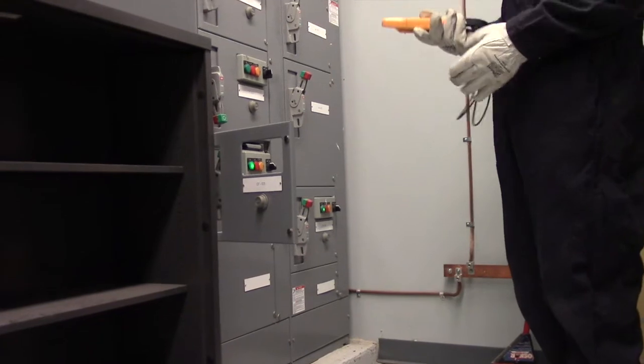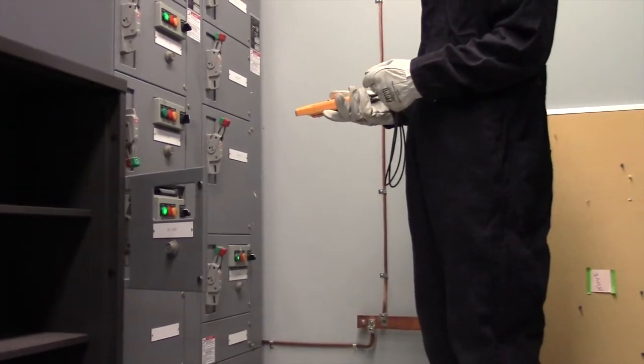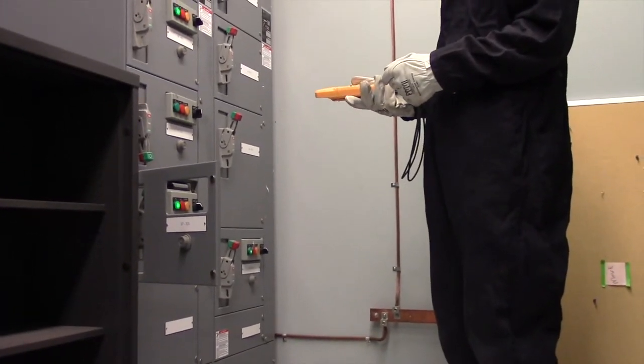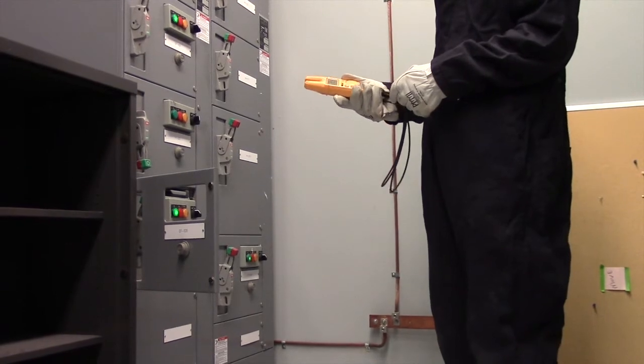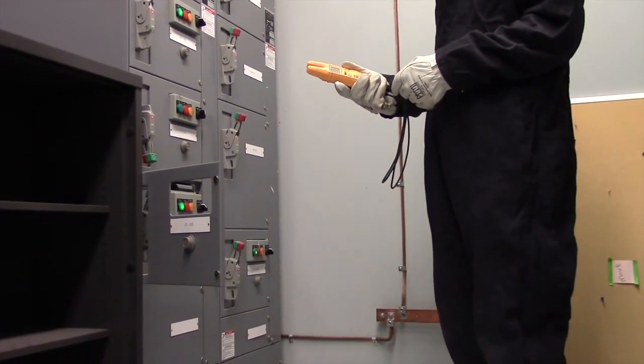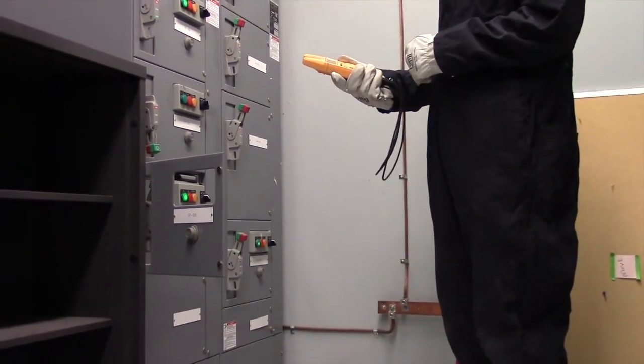Here we have an exhaust fan running on the roof. We're going to confirm the three phases are all running the same current and check the voltage at the same time.